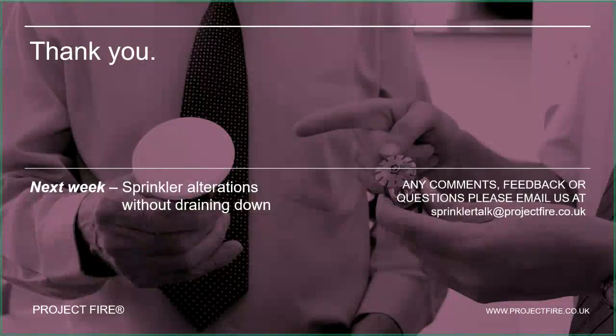Since we've got a little bit of extra time today, I'll explain a little bit more about what that is all about. When we want to do anything to our sprinkler system, if we want to drill a hole within the pipes, then we need to drain it down. I'm talking about wet sprinkler installations. If it's a dry installation, then you would still need to take precautions, because if you were to drill into the dry pipework, the air is going to be expelled, and that's going to be like a sprinkler head in operation.